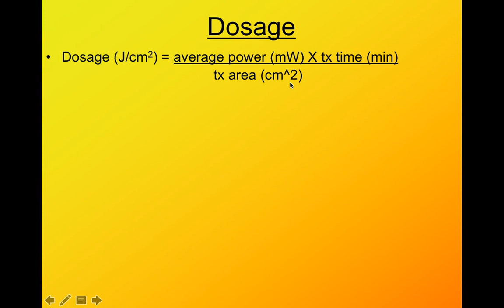And you got to know, is that dosages per centimeter squared, or are you just given the power and then you have to do the math here? So these are some examples of typical treatments that you see based on the amount of power over the area. And sometimes it's called just point, and that's typically the same as centimeter squared, because typically that one single point is a 1 centimeter squared laser probe.